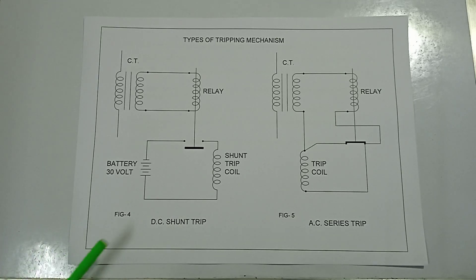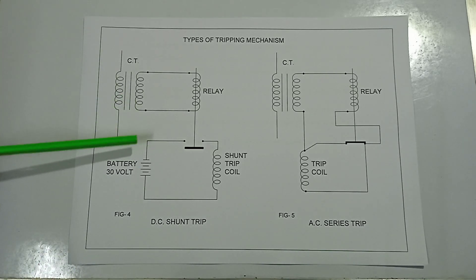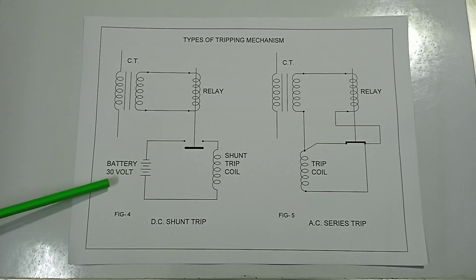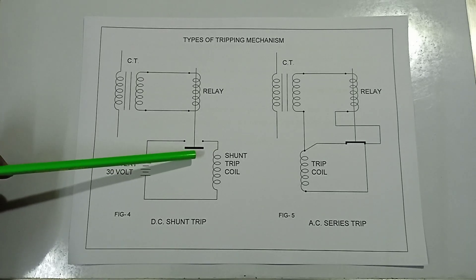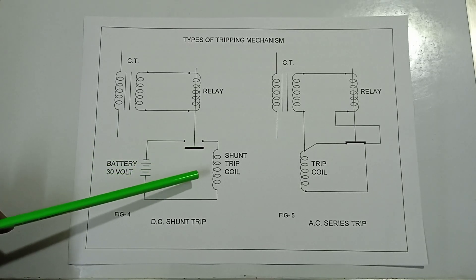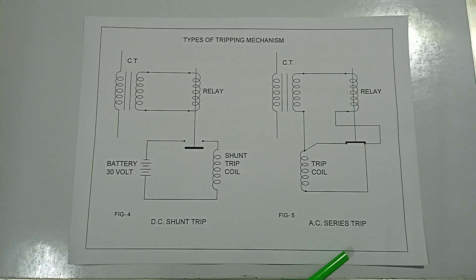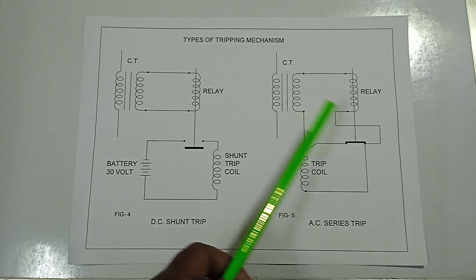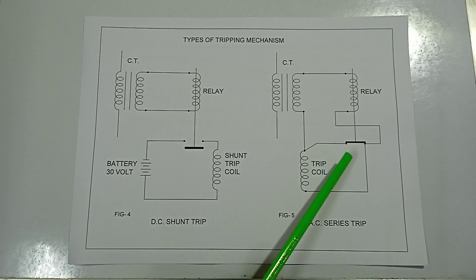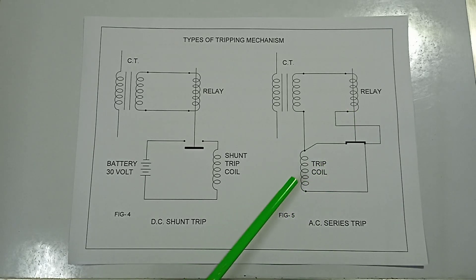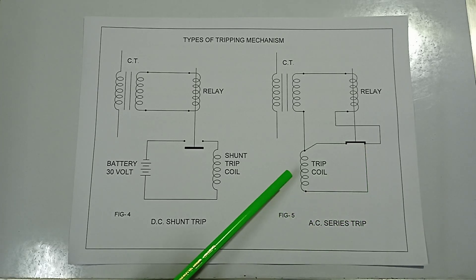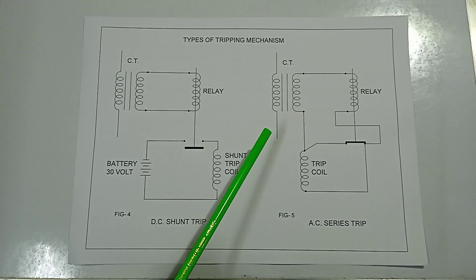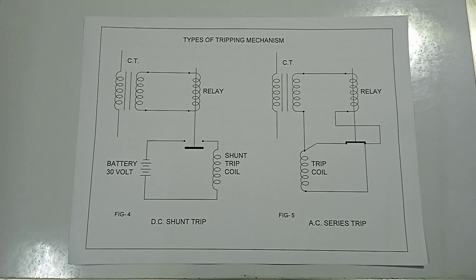In the DC shunt trip circuit, the battery energizes the relay; when the relay contact closes, the shunt trip coil is energized. In the AC series trip circuit, the trip circuit is normally shorted by the relay contact. When the relay is energized by the CT, it lifts the contact, and the trip coil is energized by the same CT current, activating the tripping mechanism.